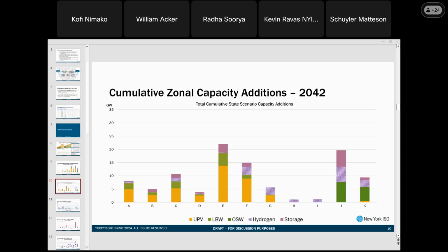But on storage, that's not the case. The actual impact of storage is dependent on when it's charging and when it's discharging to determine which might be driving the headroom. A lot of the headroom binding hours are actually low load hours, and so it's mostly the charging of storage that would be impacting those headroom hours. And same with the opposite side of things, where it's the middle of the day when the solar is really injecting. It's using that headroom to inject, but storage might actually be reducing the impact on the system by charging during those times.